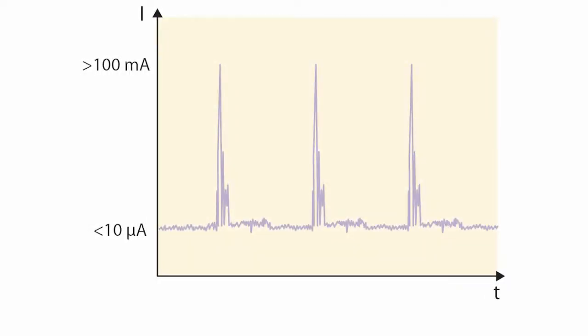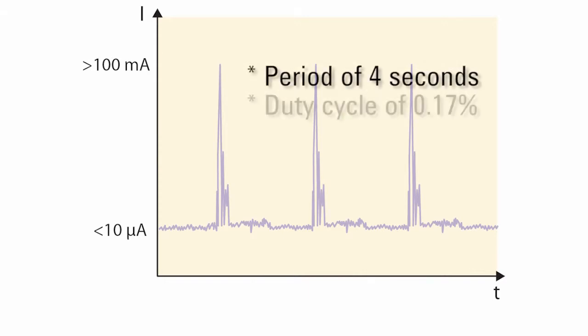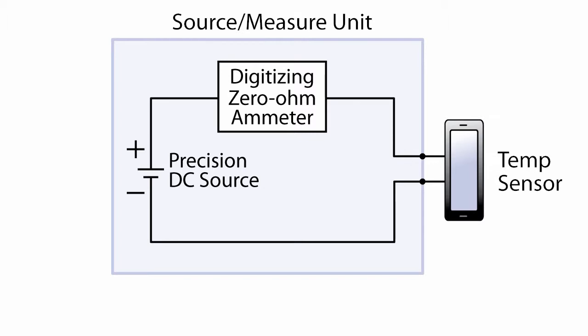In the following measurement example, the battery drain current of a wireless temperature sensor has the following characteristics: period of 4 seconds, duty cycle of 0.17%, crest factor of 400. The N6781A SMU was used to both power the temperature sensor and to measure the sensor's current consumption. The internal 0 ohm ammeter is key to precise measurements of low-level current.